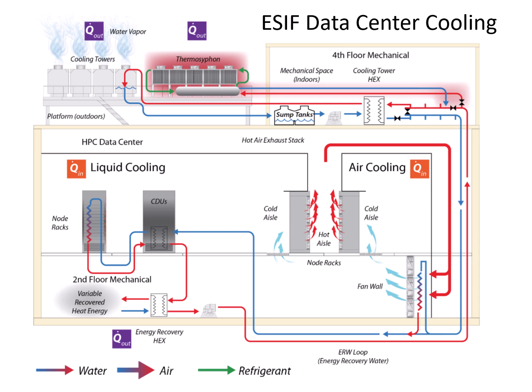They do have a thermal siphon system that reduces pumping power, evaporative towers when needed, and dry coolers when available. They call them adiabatic cooling towers, with a dry cooled closed circuit that sprays water on the outside only for limited hours of the year. So there's a lot of HVAC cooling innovation making these things more efficient, but I think no mechanical chillers with liquid cooling to the rack is the future.